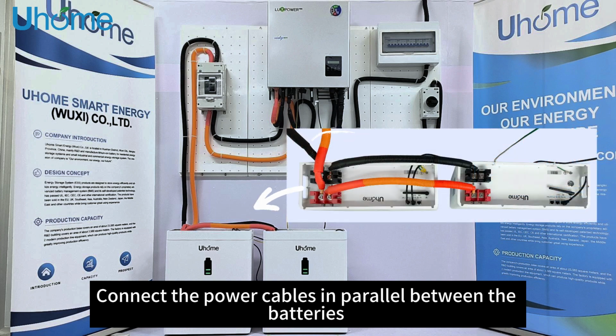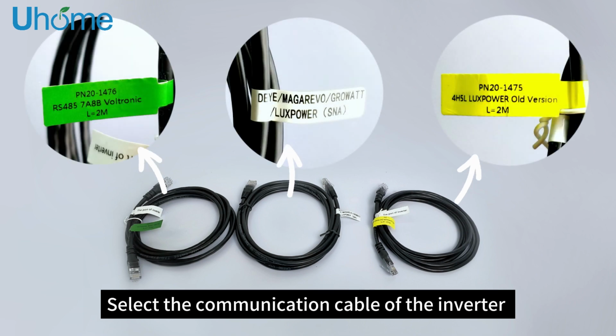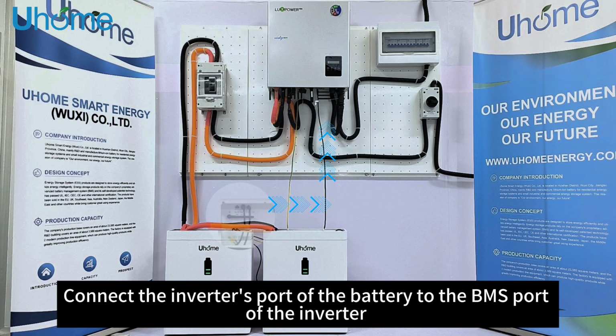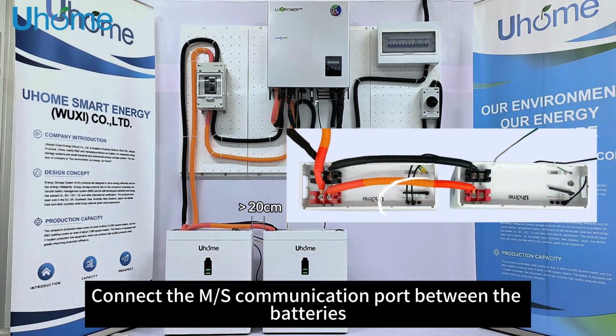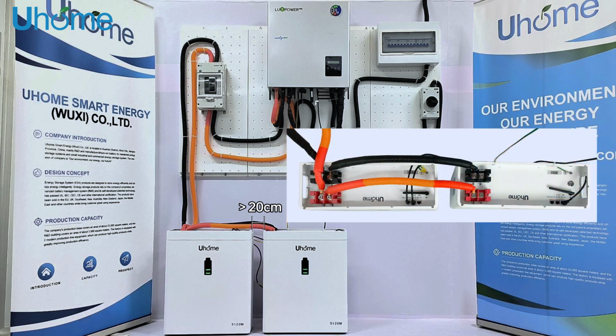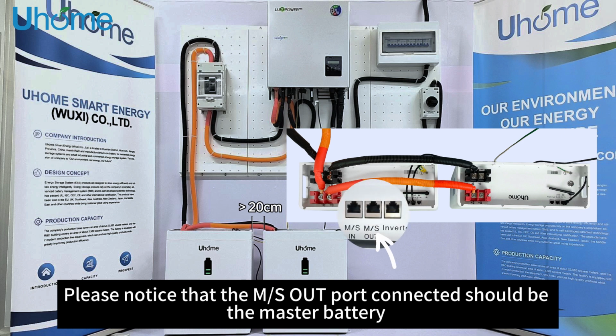Connect the power cables in parallel between the batteries. Select the communication cable of the inverter. Connect the inverter's port of the battery to the BMS port of the inverter. Connect the M/S communication port between the batteries. Please notice that the M/S out port connected should be the master battery.